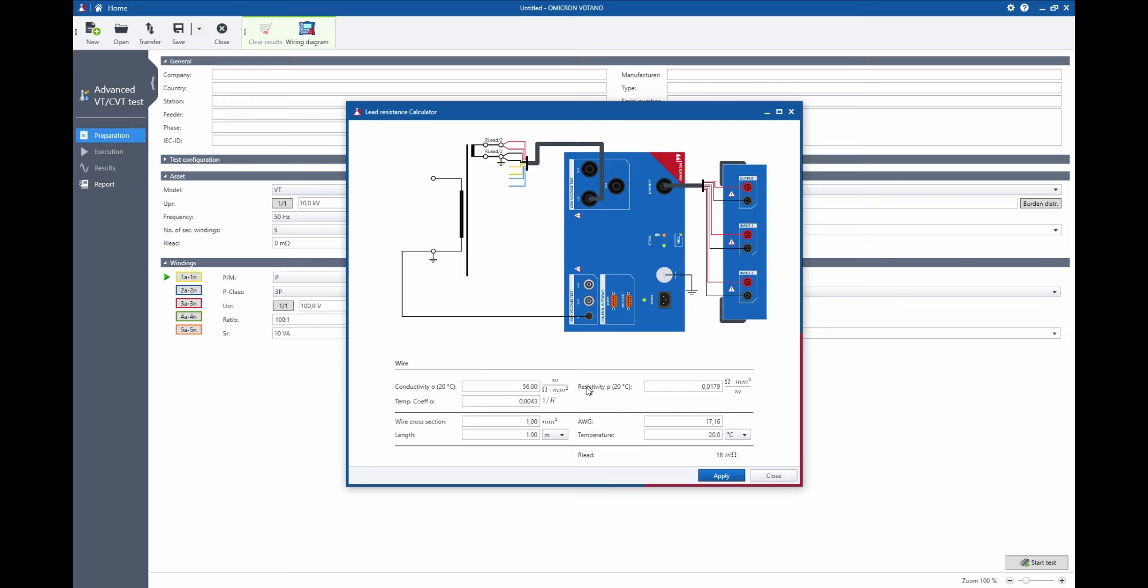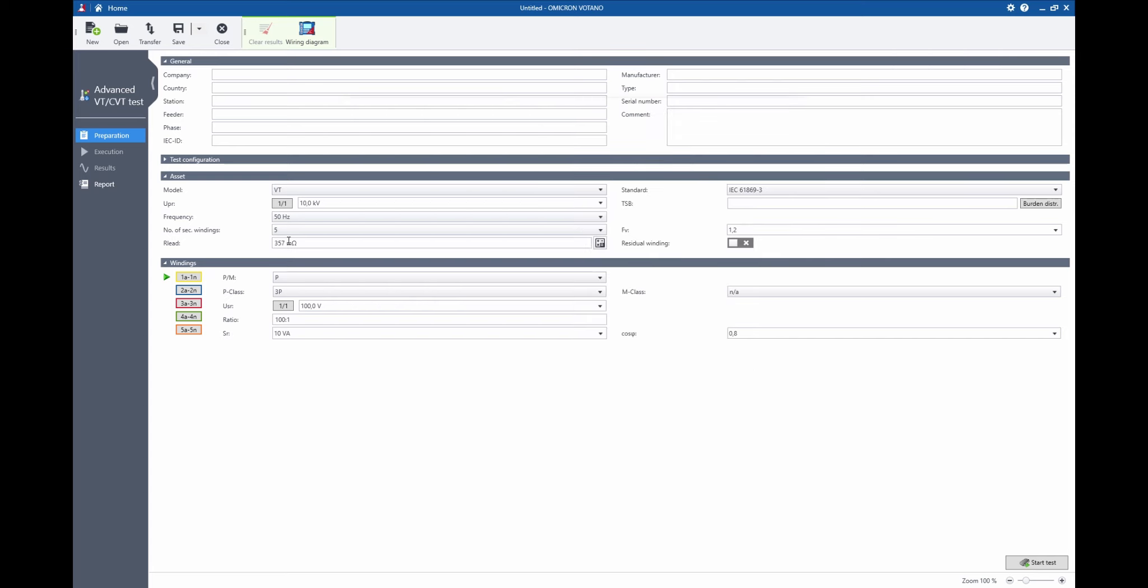And with this tool I can estimate for a certain set of wire parameters, like a certain length and a certain wire cross section, the lead resistance and directly apply it to my measurement. Like this it will not affect the accuracy of the end result because this lead resistance will be considered or eliminated from the voltage drop as we would observe it directly at the terminals of the VT.